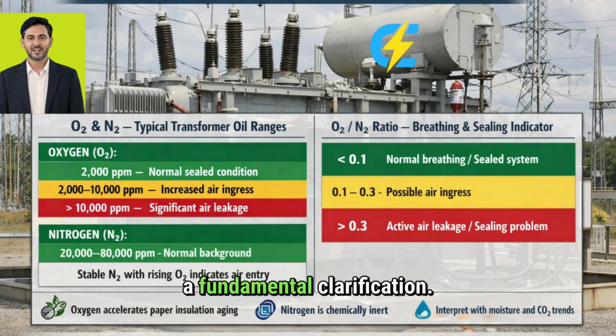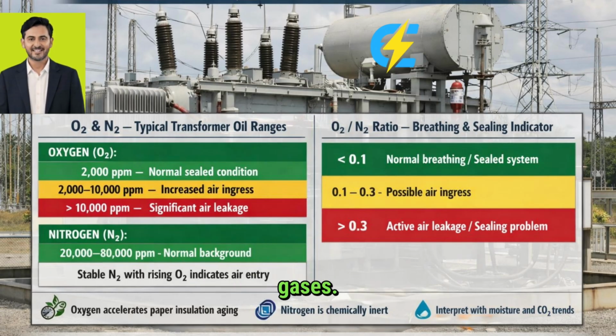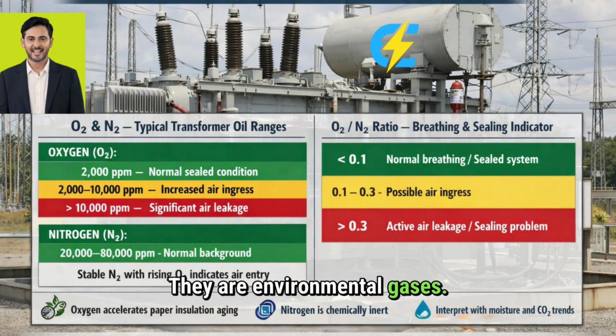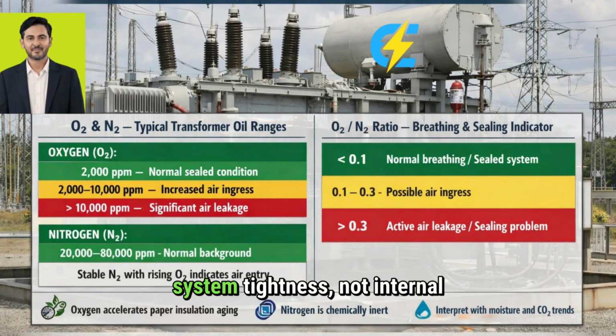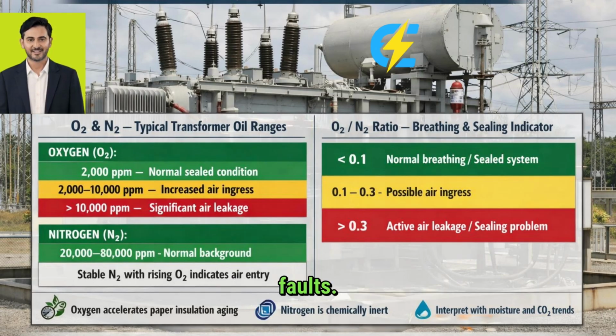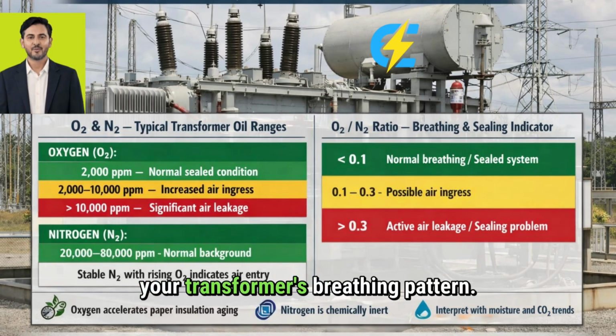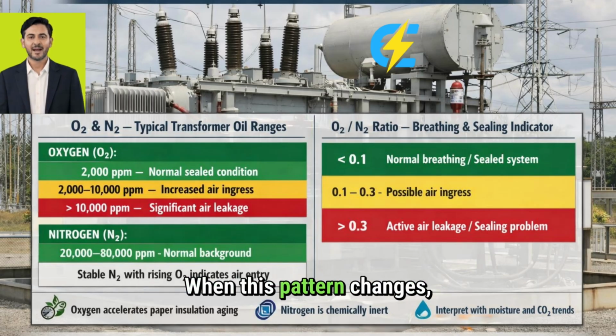Let me start with a fundamental clarification. Oxygen, O2, and nitrogen, N2, are not fault gases. They are environmental gases. They tell us about system tightness, not internal faults. Think of them as your transformer's breathing pattern. When this pattern changes, it reveals whether your equipment is properly sealed or slowly suffocating under poor maintenance.